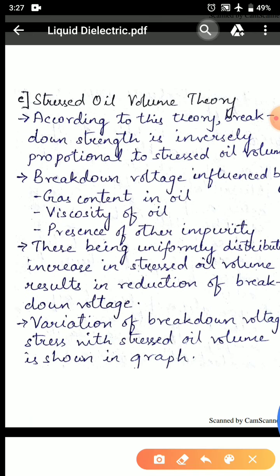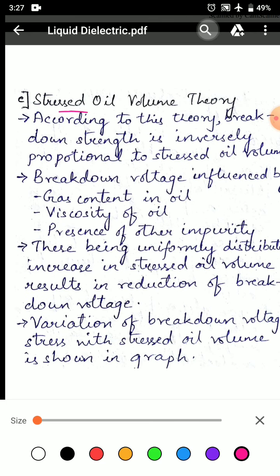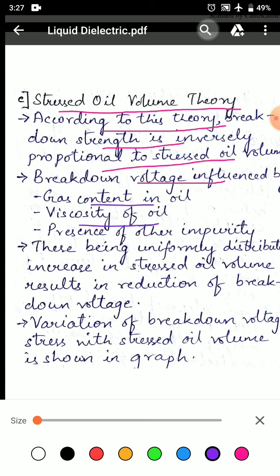The third type of theory or mechanism is stressed oil volume theory. According to this theory, breakdown strength is inversely proportional to stressed oil volume. The breakdown voltage is influenced by gas content in oil, viscosity of oil, and presence of other impurities. These being uniformly distributed increase the stressed oil volume, resulting in reduction of breakdown voltage.